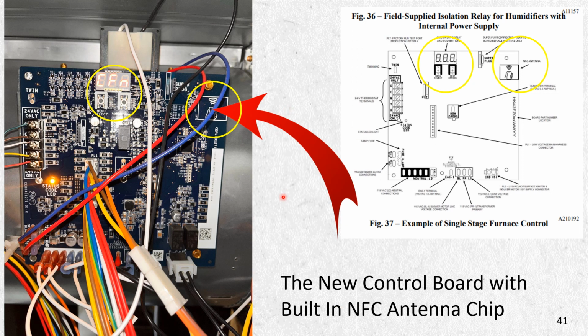Now what you're looking at is the actual board that is in the N80s MSN and the N92s, 96s MSN. This is the communicating or programmable board. As you can see, I've got two circles right here. This will have an LED light. If you're going manual, you'll have two buttons here to set the board. Now, like I said, this unit will come on and run on the factory specs that it has, whatever model you have. It'll show up right here what your speeds are when you press this button. You'll go through the menu options, and then you hit this one, and that's how you change your speed.